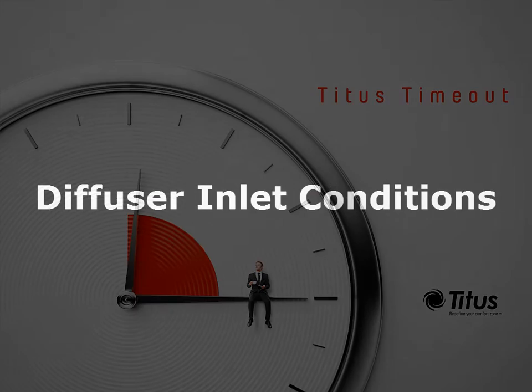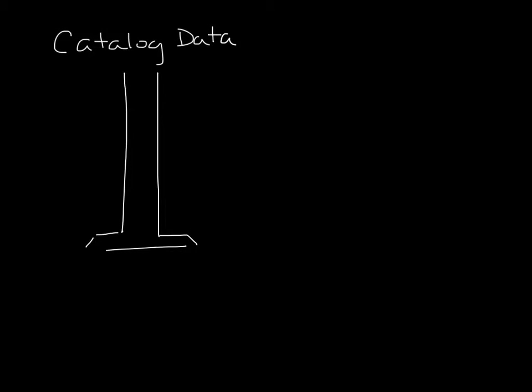I'm Jenny Abney-Civy, and today we're going to discuss how diffuser inlet conditions affect performance, especially sound. Diffuser catalog data are based on ASHRAE test standards that require 10 equivalent duct diameters into the inlet. This is great for getting repeatable data that could be compared between manufacturers, but not very realistic. When was the last time you had 10 equivalent duct diameters in a ceiling plenum?